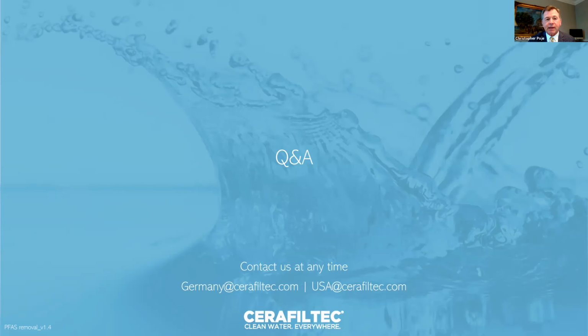The interesting thing, I think we need to differentiate between granular activated carbon and trying to remove an entire bed of that and regenerate that much media, and looking for breakthrough at 9 months or 18 months or whatever the case, and all the downstream safeguards against that, because the powdered activated carbon is used so sparingly and in such a targeted manner and replaced so often. We can literally design the process so that you never have breakthrough and the minimal amount of carbon is used. So the waste disposal, while it's going to be a material quantity, especially in a plant as big as Rome, it's 18 million gallons a day, it'll be a material quantity of carbon. It'll be far less than the other waste streams that you'd see in alternate technologies.